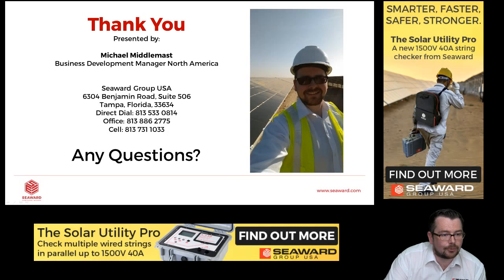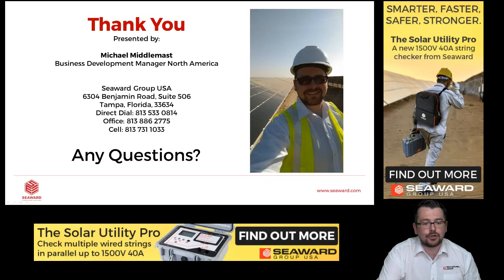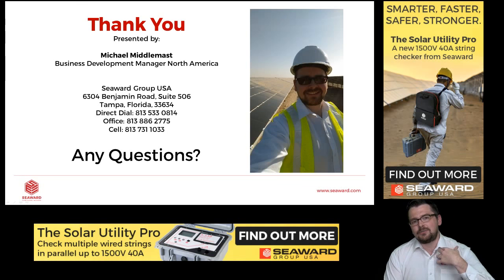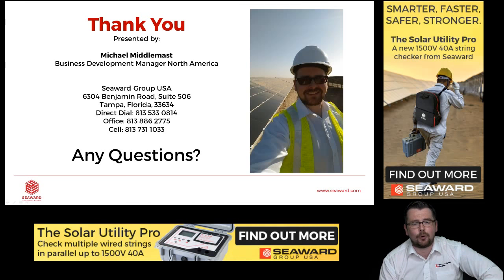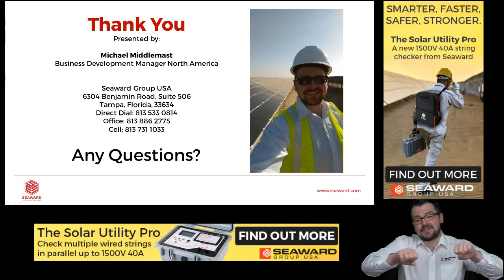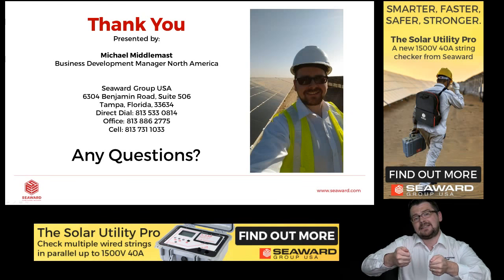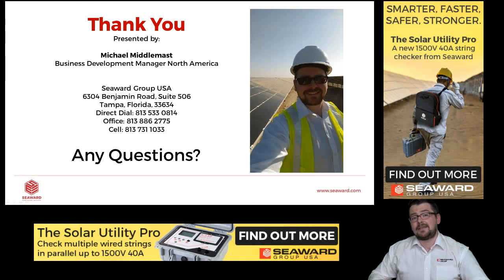Can you take a moment to discuss troubleshooting on systems with DC optimizers, asks Sean Taylor. Sean, unfortunately, there's very little we can do to interact with DC optimizers. Once they're disconnected from the inverter, they only output a single volt. And this is part of the rapid shutdown requirement for residential systems. So there's not particularly too much we can do with our instruments to interact with DC optimizers. However, systems such as SolarEdge have very good diagnostic tools built in within their monitoring platform, so you can always check that. Or you could also disconnect each individual DC optimizer, connect in the tester, and test the panel bypassing the DC optimizer.